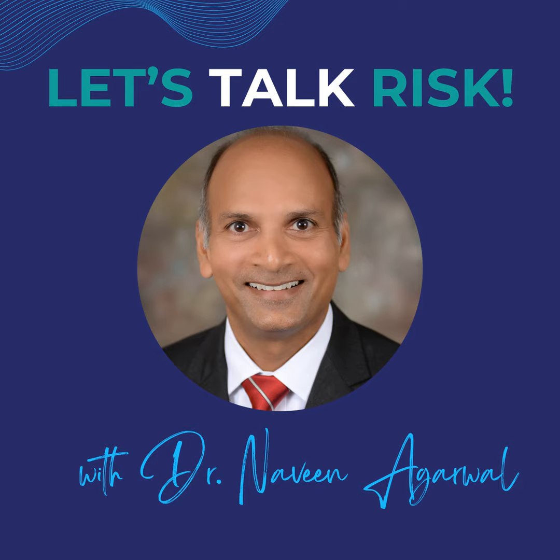Well, you can assume 1 for everything, but what you might find is that then the outcome that you're trying to avoid, so the harm that you're trying to avoid, if your P1 is 1, then there's a certainty of some sort of harm. Now, it may be that in your risk acceptance, that harm is considered to be minor enough that it's acceptable without reduction, but likely not. So the important thing is calling out the individual steps, or the individual elements of the sequence, so that you can concentrate on where you're going to reduce that.